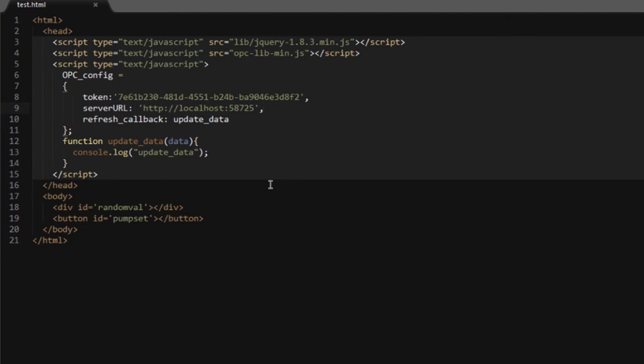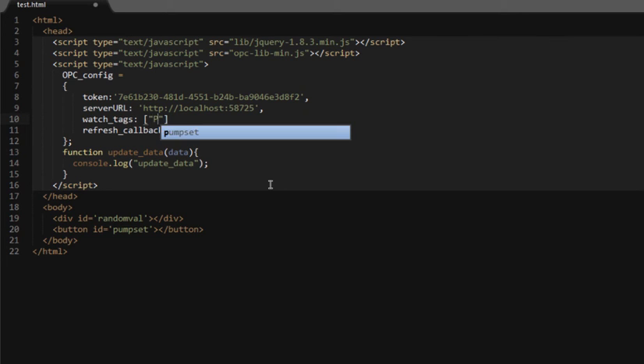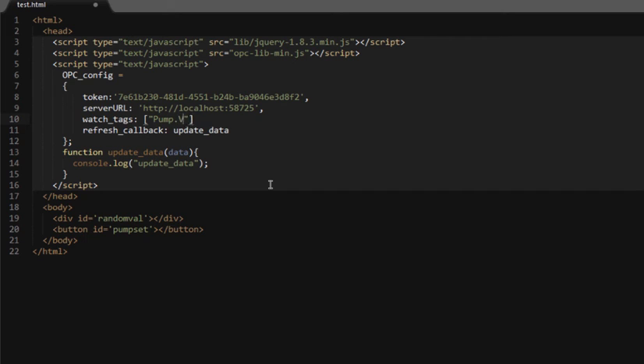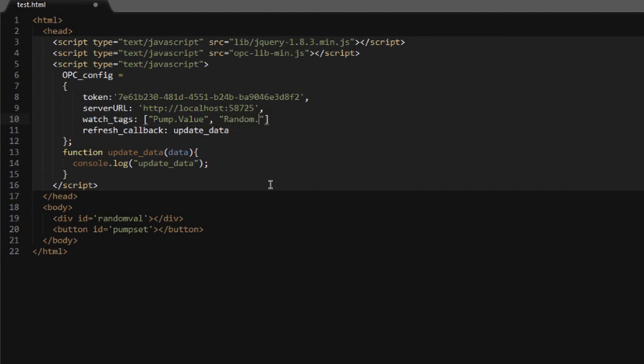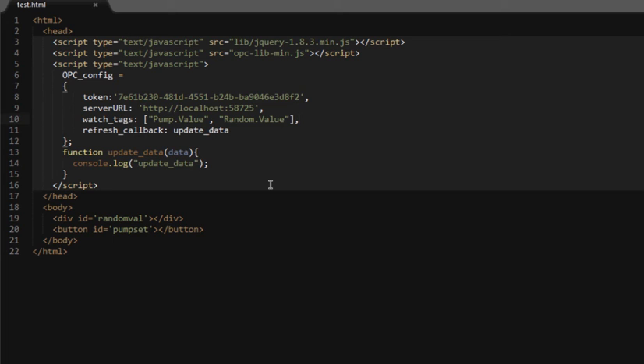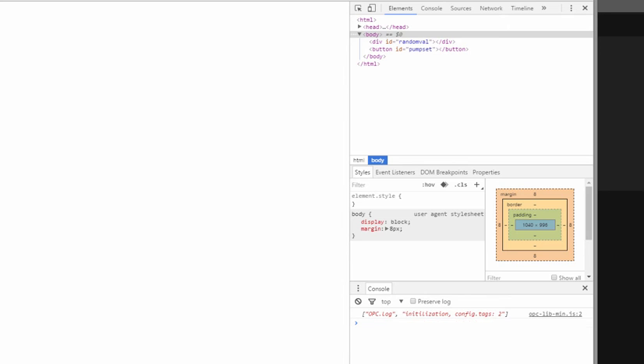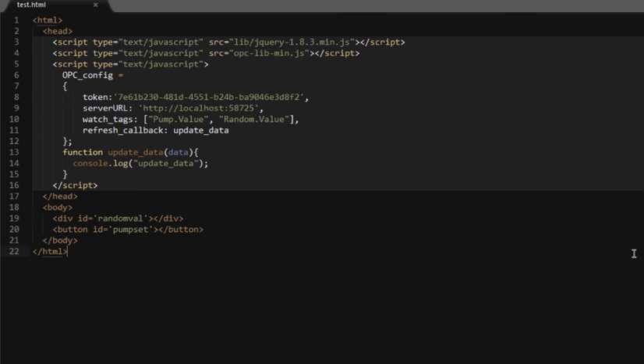The system will not update or callback to the server unless we're monitoring tags. To do this programmatically, we add a watch tags array to the config, and we list every single tag we want to monitor. In this case, we're going to monitor the same two tags, pump.value and random.value. Go back and refresh now, and what we should see is update data being called. Now that we know the communication from the client to the server is working, we're monitoring those two tags. Now we can start making changes on screen.